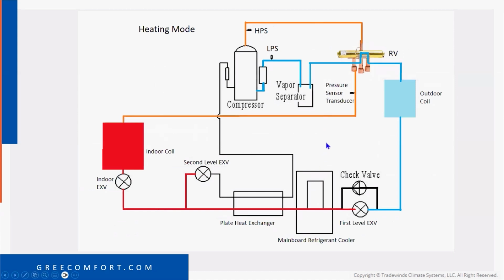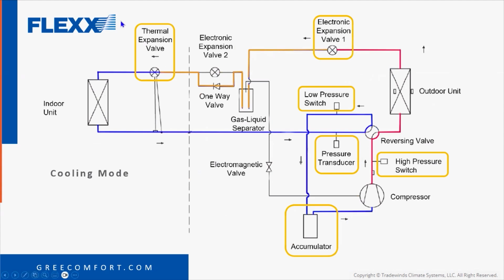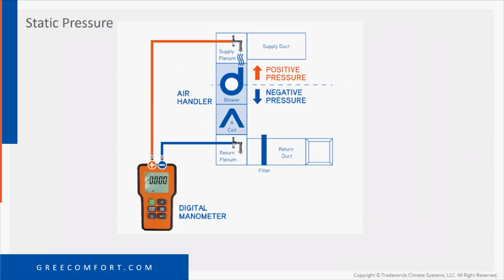We don't have an electromagnetic valve, but we do have the EEV for the plate heat exchanger, and that's where they're getting low ambient operation from. So I kind of like it because we get rid of this big cylinder in here that we don't necessarily have to have, which actually makes things a little better. So now what we're going to do is we're going to move to the equipment and less to pictorial, and we'll come back to the owner's manual / installation instructions as well.